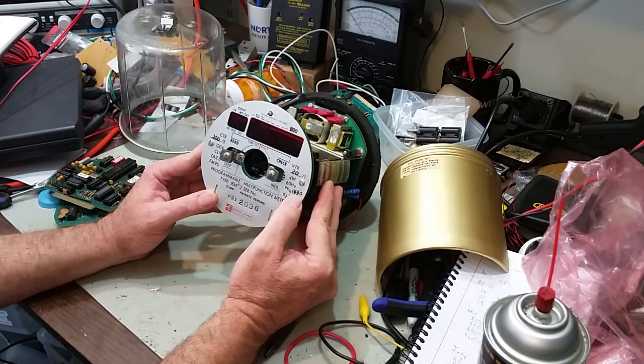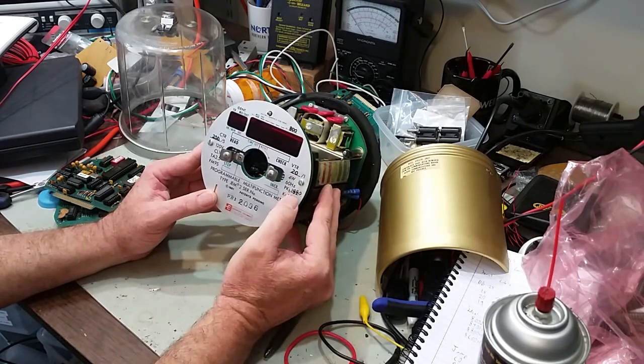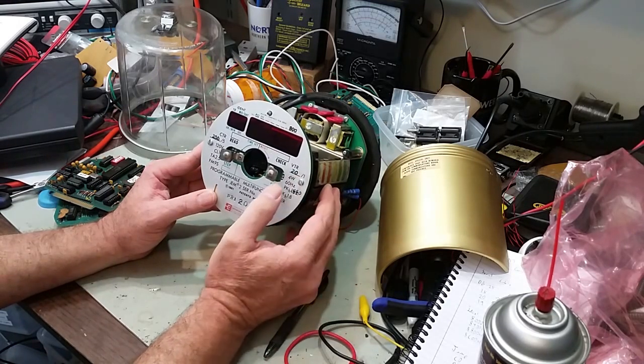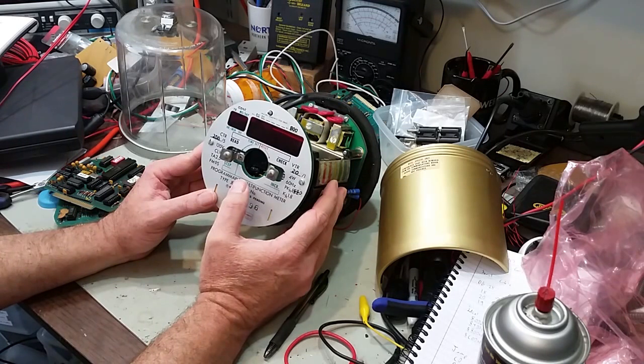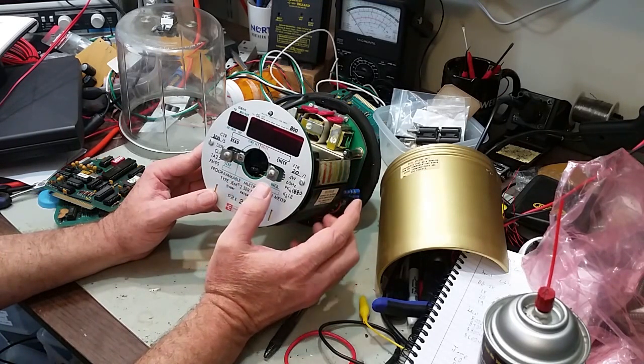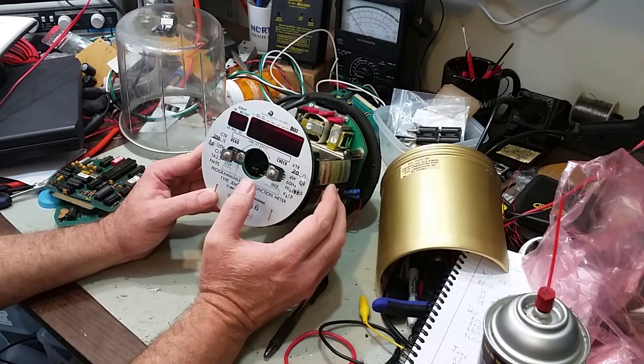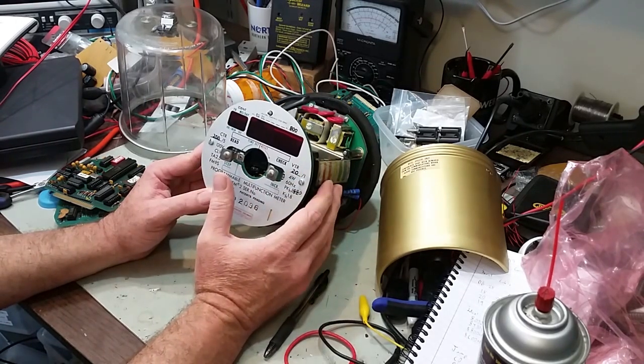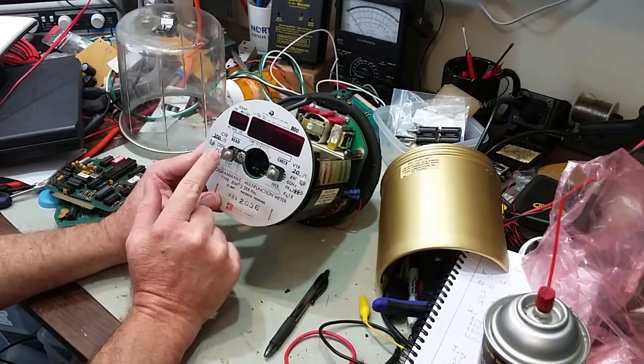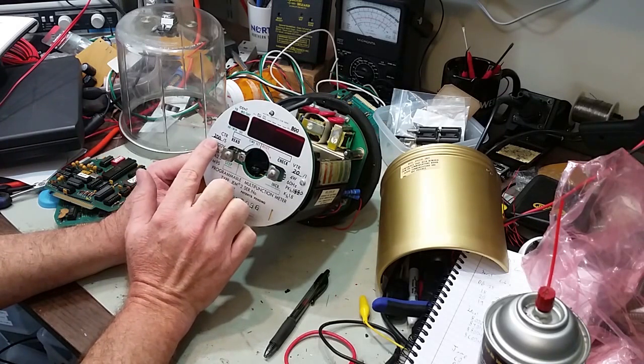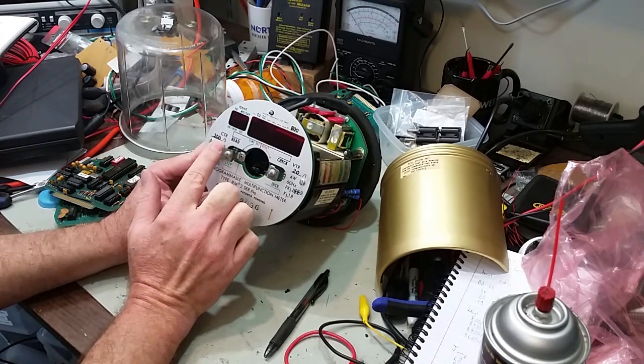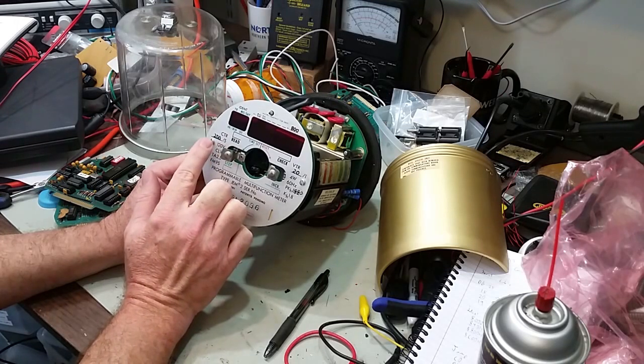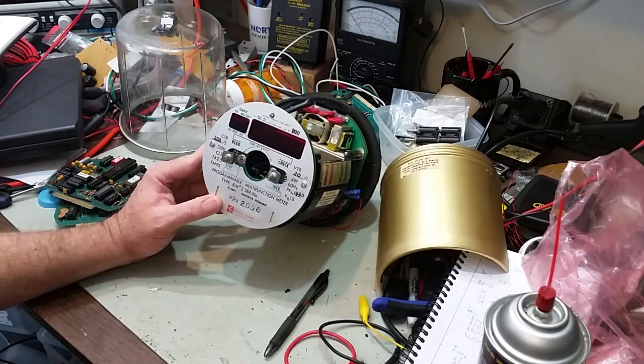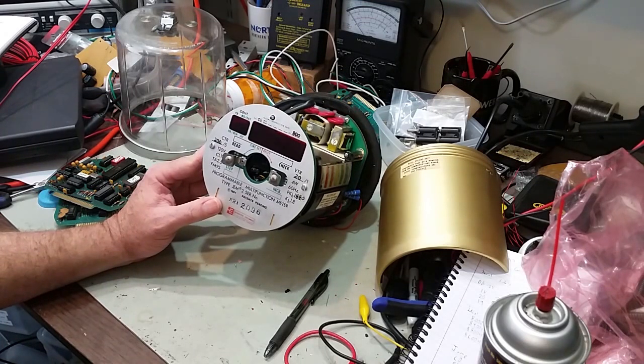There's information here about the multiplier. The voltage transformer ratio was 20-to-1, so when this was measuring 120 volts, the actual voltage on the step-down instrument transformer would have been 20 times that, or 2,400 volts. The current reading had a CT, current transformer, that was 200 to 5, so when this was seeing 5 amps, there was actually 200 amps flowing through the core of the instrument transformer.